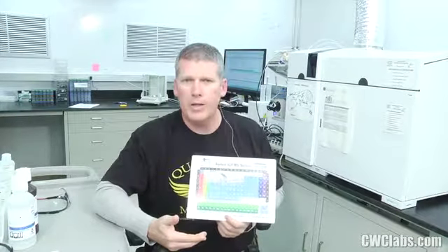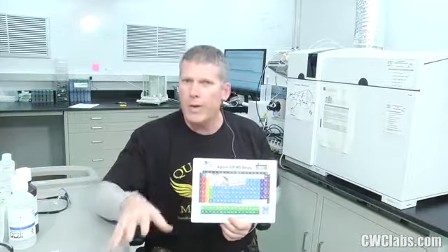So here's a very big one. I call this the polyatomic overlay interference with the internal standards, causing the apparent reduced concentration of the analytes in your samples. The way to find this problem is if you have a specific mass range of analytes that consistently shows low numbers in your run, where other masses or other analytes look good.